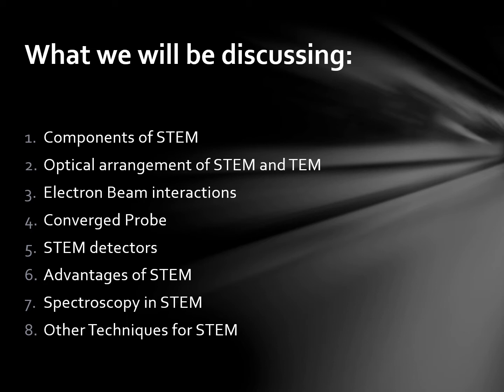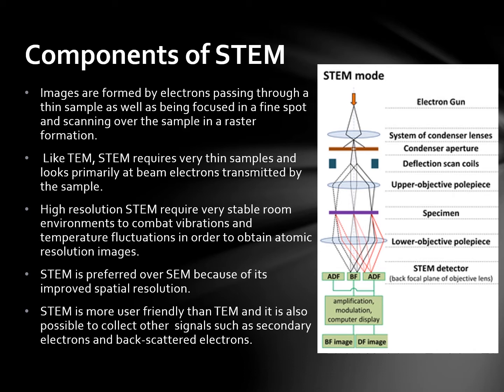Images are formed by electrons passing through a thin sample, focused in a fine spot and scanning over the sample in a raster formation. Like TEM, STEM requires very thin samples and looks primarily at beam electrons transmitted by the sample. High-resolution STEM requires very stable room environments to combat vibrations and temperature fluctuations in order to obtain atomic resolution imaging. STEM is preferred over SEM because of its improved spatial resolution, is more user-friendly, and it is also possible to collect other signals such as secondary and backscattered electrons.